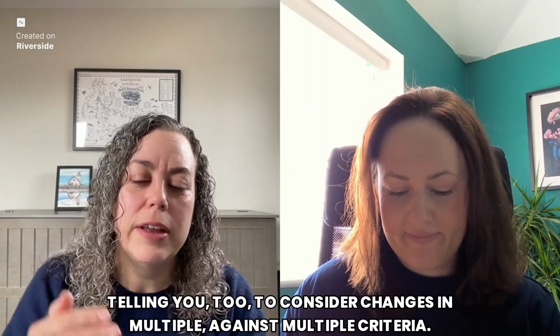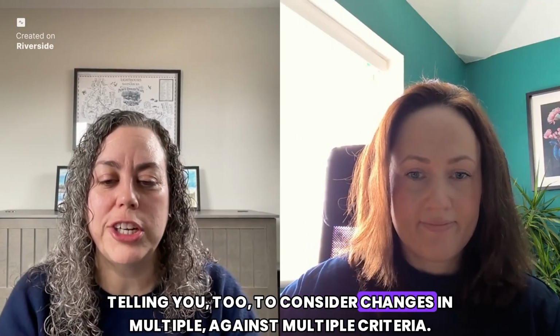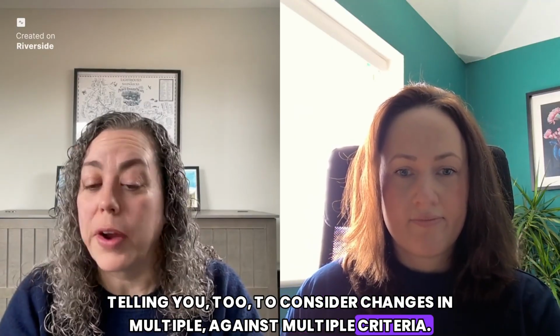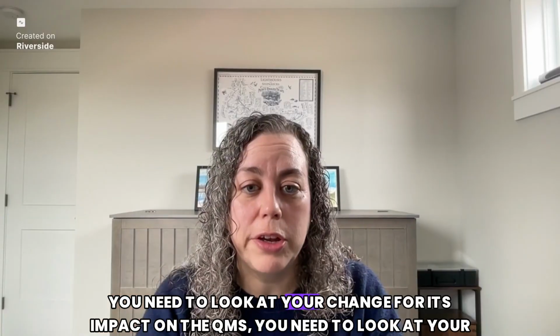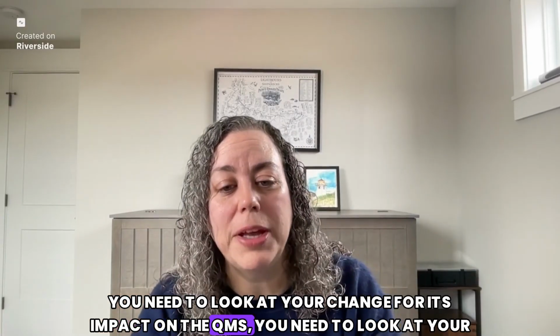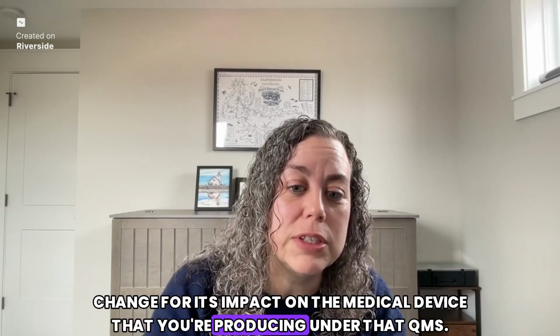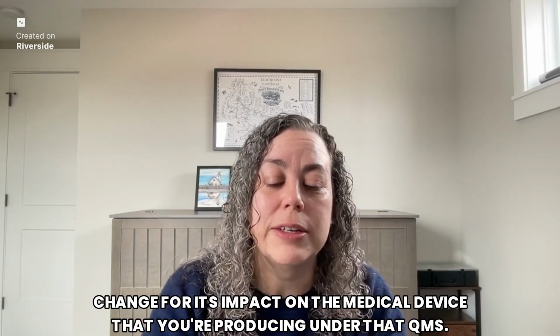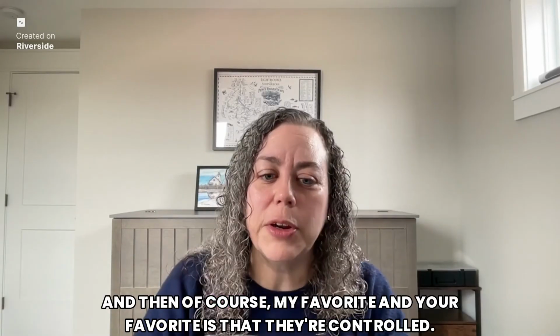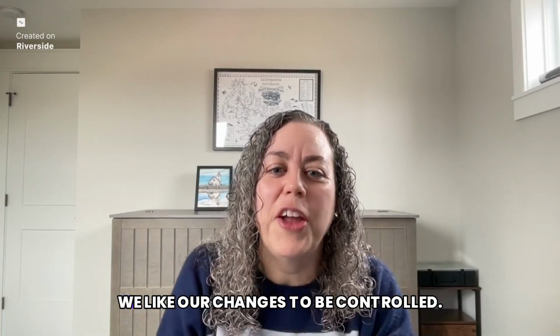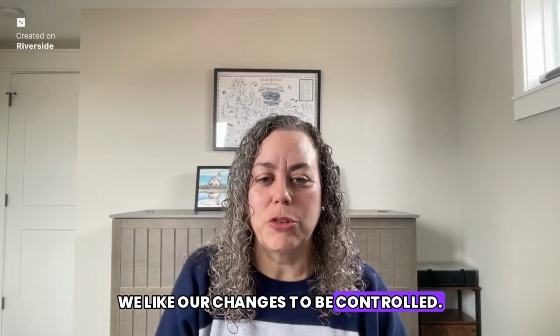So it's telling you to consider changes against multiple criteria, right? You need to look at your change for its impact on the QMS. You need to look at your change for its impact on the medical device that you're producing under that QMS. And then, of course, my favorite and your favorite is that they're controlled. We like our changes to be controlled.